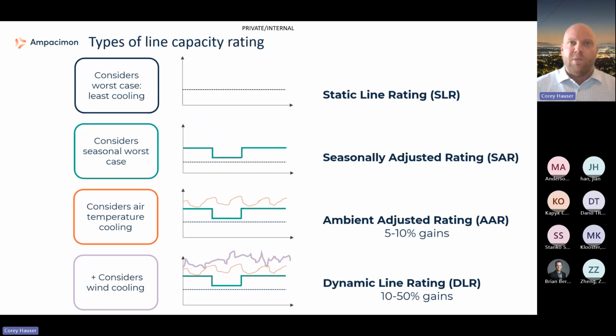Typically, most will have likely moved on from a static line rating to some sort of seasonally adjusted rating. This is where you're getting above the static line rating and factoring in some different temperature metrics, but you're not quite getting to the granularity of an ambient adjusted rating, especially with FERC 881, where we're looking at it on an hourly basis. So this is when you're going by season and ambient temperature, where you're going to have a lower rating in the summer or in the winter, and in the summer it's going to be a lot harder when you have those peaking loads.